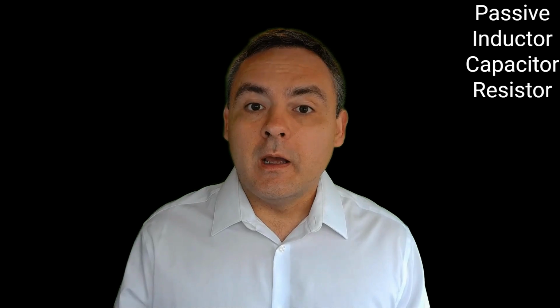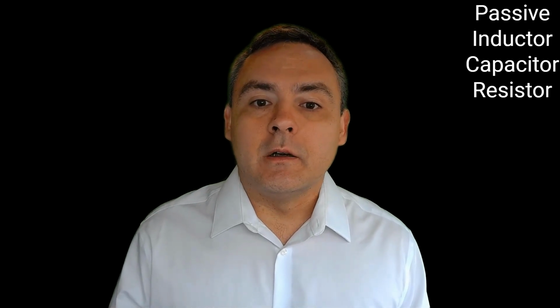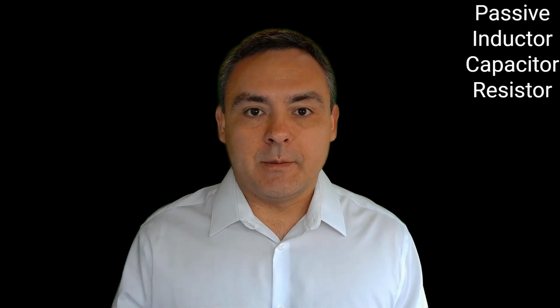We have only looked at passive harmonic and power quality mitigation devices in previous videos. By passive, I mean an inductor, a capacitor, a resistor, or some combination of these devices. Modern active harmonic devices use a switching device to control harmonics. The switching device is almost always an IGBT. An IGBT is an insulated gate bipolar transistor. They are practically an ideal device for higher voltages and currents.